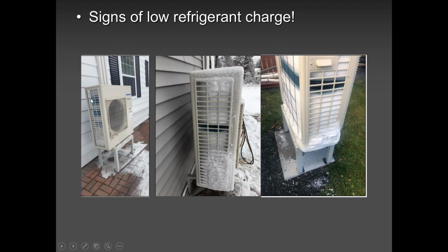Here, this unit was low on refrigerant by 2 pounds. This one, I think 1.6 to 1.7. This one, I can't remember, but they are from 3 different regions. I put these pictures so that when you come across this kind of picture, the unit went into defrost and came out quickly because it exceeded its 10-minute time, and there was not enough refrigerant, hot gas, to melt all that coil.